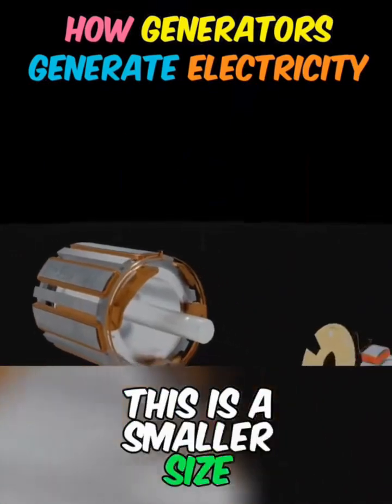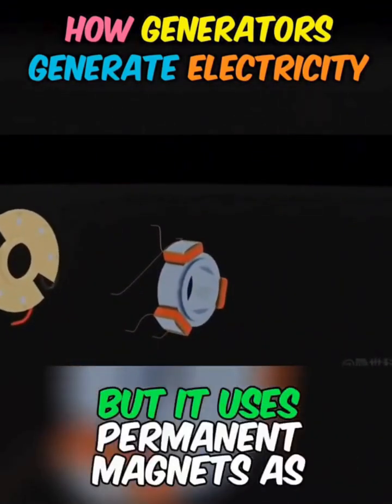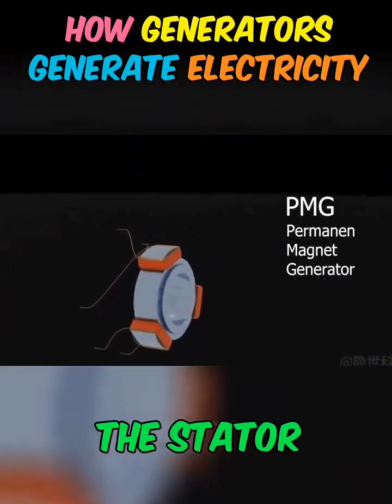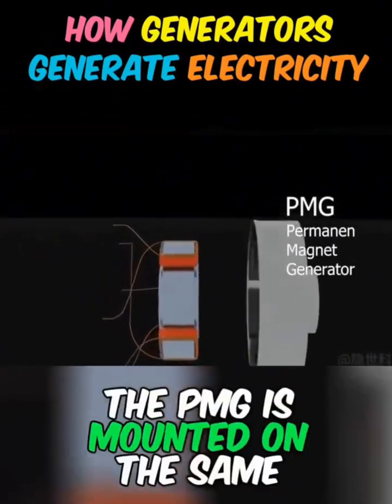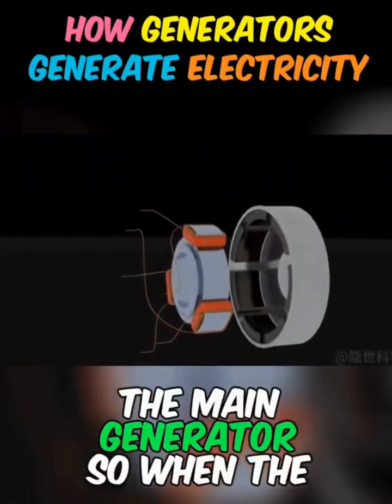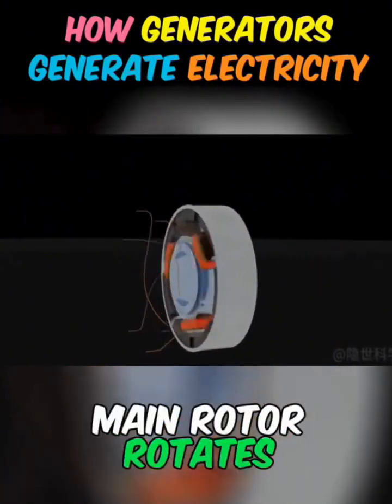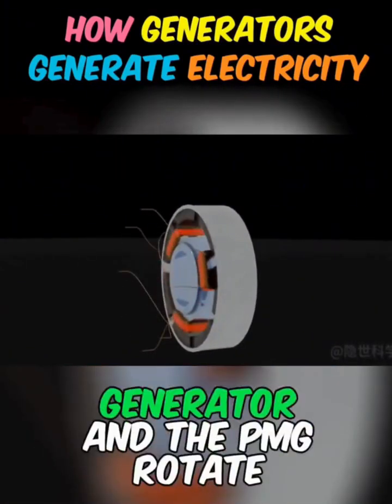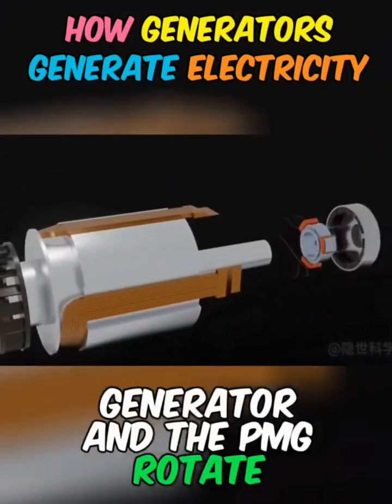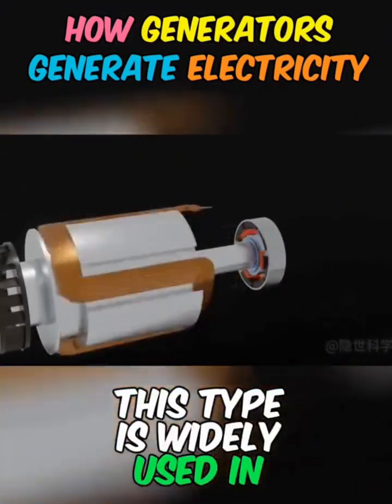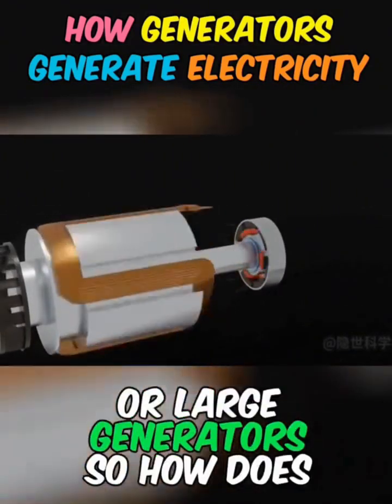This is a smaller size generator, but it uses permanent magnets as the stator. The PMG is mounted on the same shaft as the main generator, so when the main rotor rotates, both the rotors of the generator and the PMG rotate. This type is widely used in generator sets or large generators.